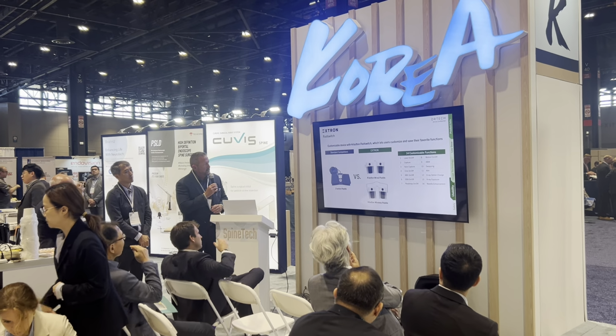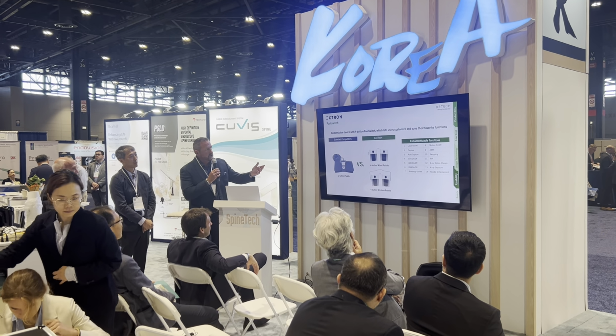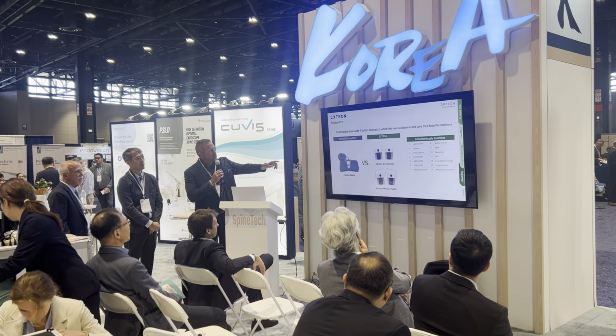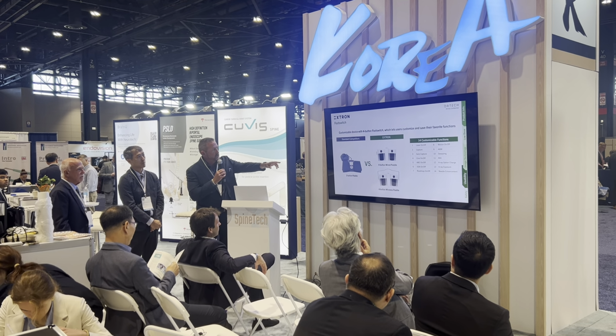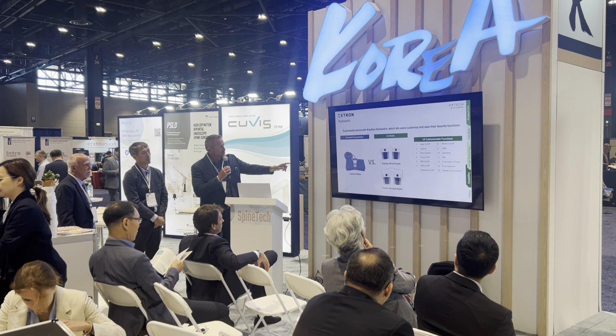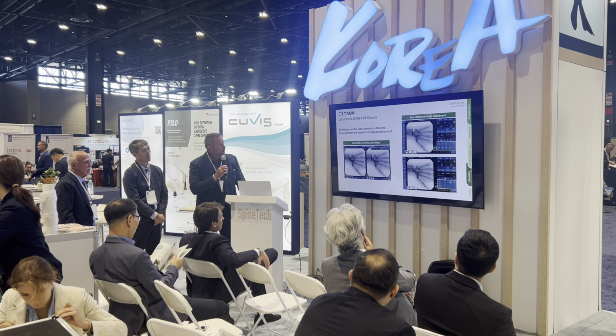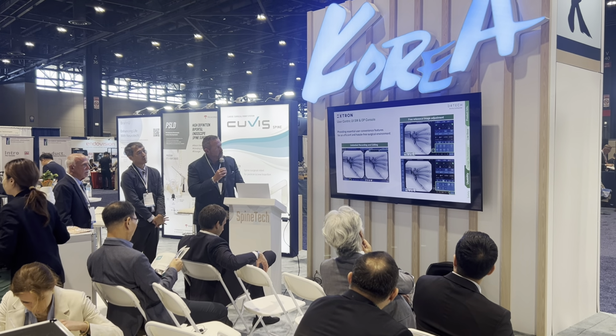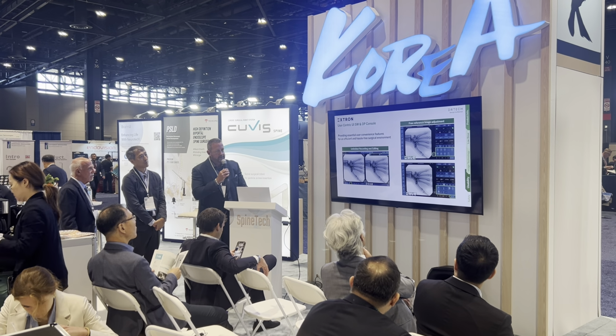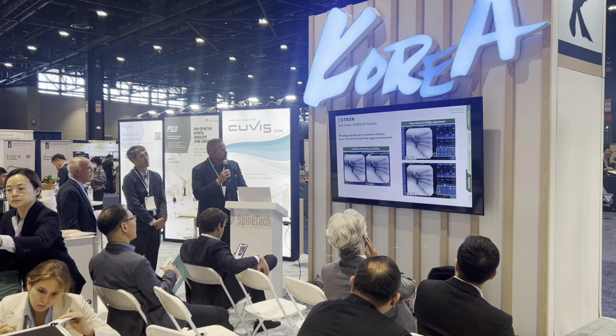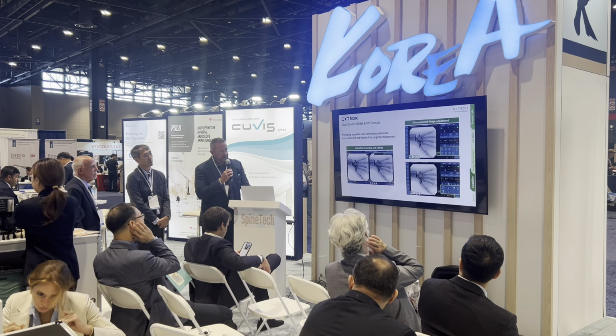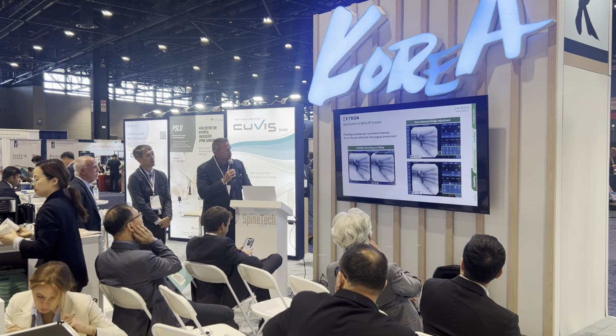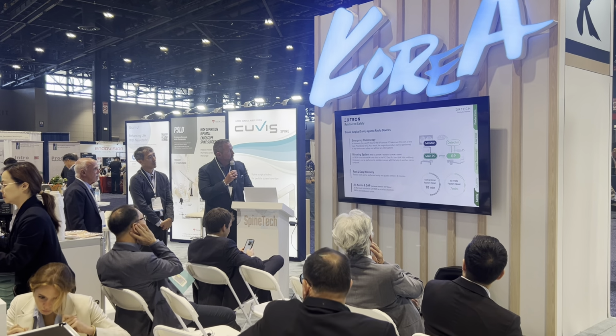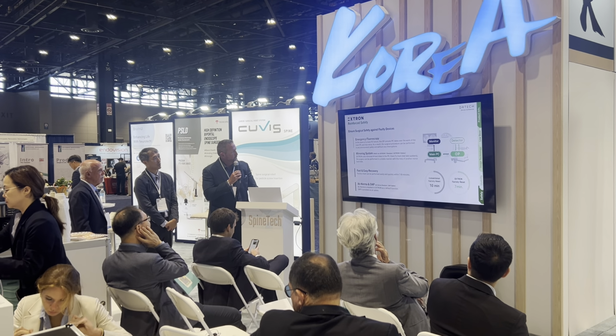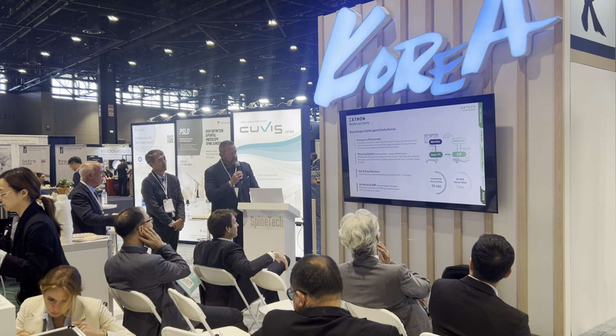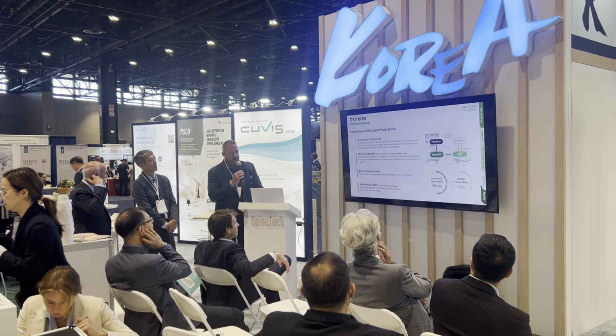Wireless foot control can be programmed to 14 different functions. On the right, you see all the different ones, so you can assign all those 14 functions to each one of the different buttons on the wireless foot control. Unlimited recording. We have about 500,000 image storage, 1 terabyte of memory. It does have built-in DICOM. You can send right to your PACS, 2 USB ports. So it has a lot of really, really nice features. If the monitor cart goes down, you could still operate the C-arm and still do cases.